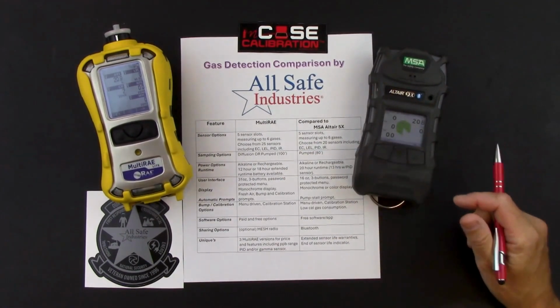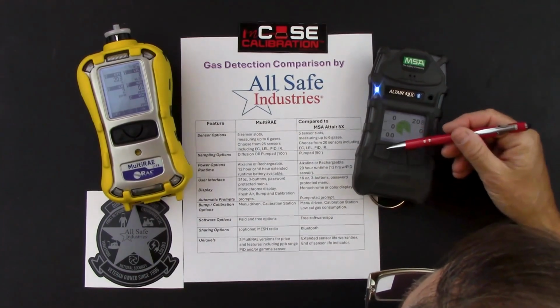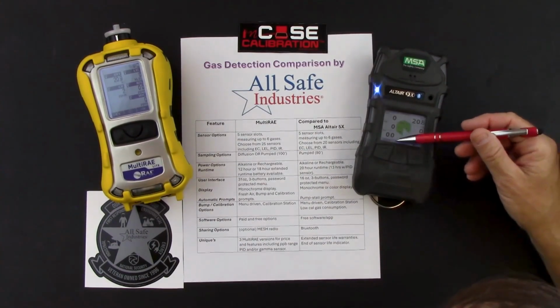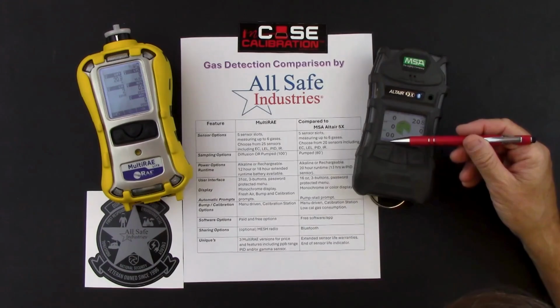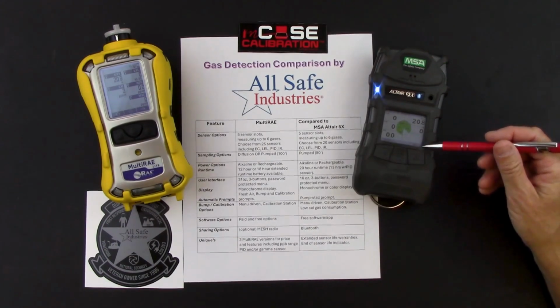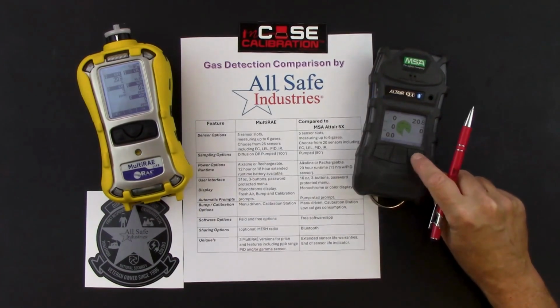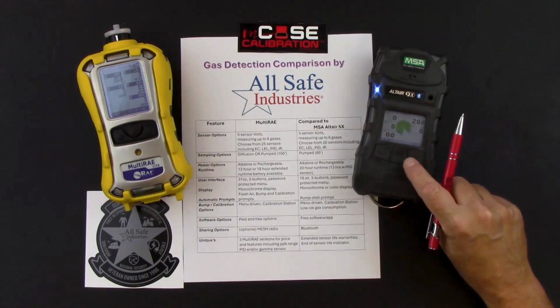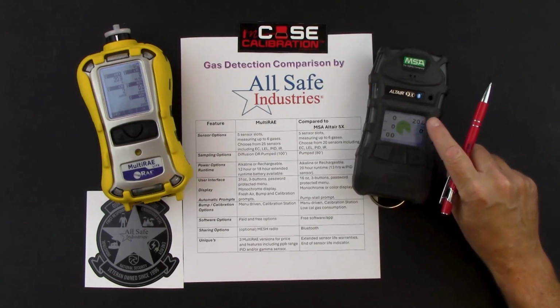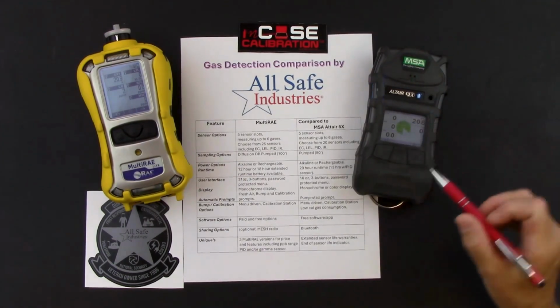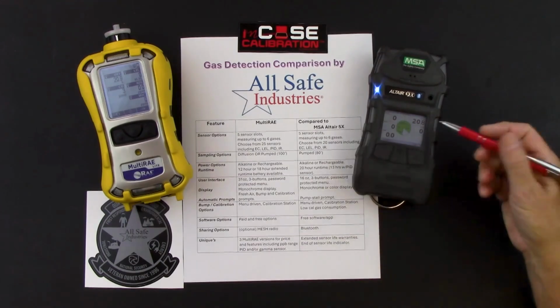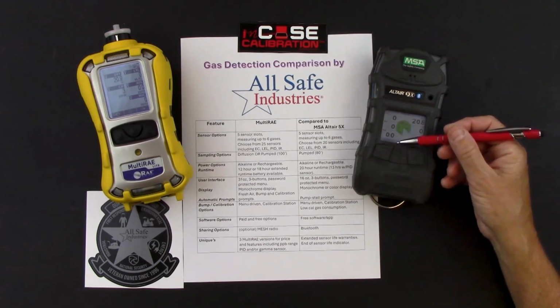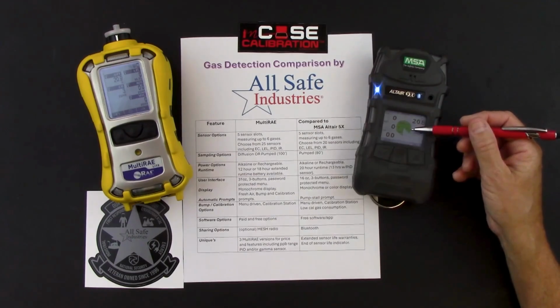same type of interface. I've got my up and down arrows, and you can see that I've got bump listed over here and calibration listed over here. If I press the calibration button, it's going to put me into choices I would make to calibrate the instrument. If I hit this button over here, it takes me to the next screen that is available on the display of the Altair 5X.